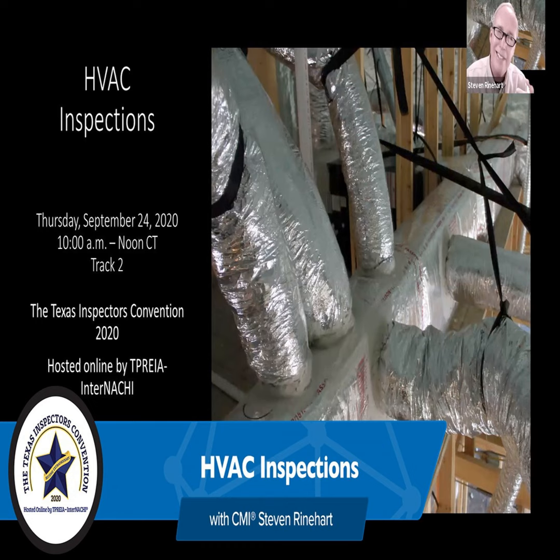Absence of a shutoff valve. Not much of a problem. I do find some old antique valves hard to get to. I might recommend replacing the valve. Usually the flex connector, yeah, if you've got the old brass connector, maybe a problem. I like the new flex connectors. And the connector should not extend into the air handler. Should have a steel little stub out, connect on the outside. Should have a flex, cut off, all those little components, drip leg.